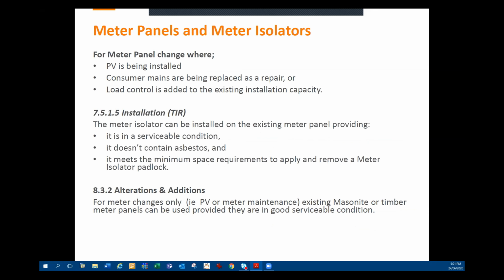For a meter panel change, where PV is being installed and the panel's being changed, then the meter isolator is required. If the consumer mains are being replaced as a repair, then the meter isolator is required. If there are extenuating circumstances, we can look at those on an individual basis, but basically if it's being replaced as a repair and can be installed, then that meter isolator needs to be installed, especially if the size of the consumer mains is being upgraded as well. And also if load control is added to the existing installation capacity.